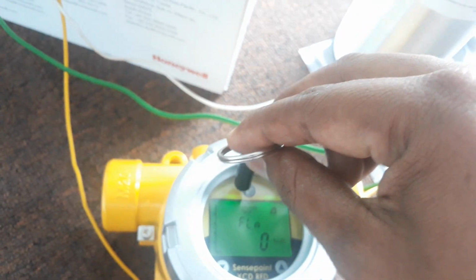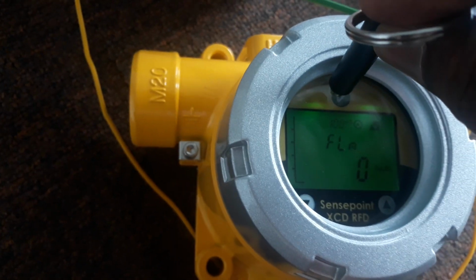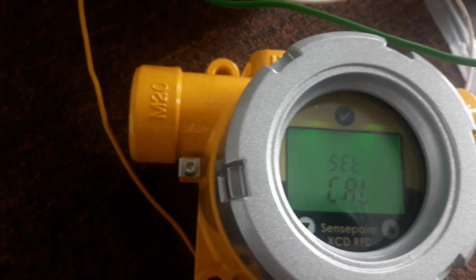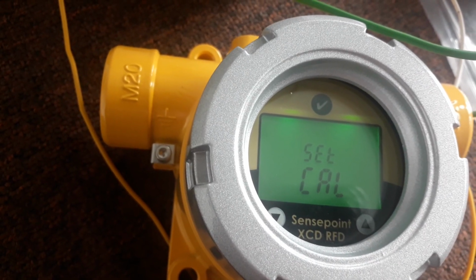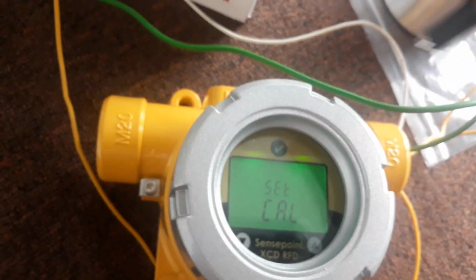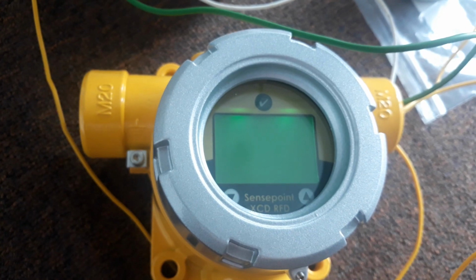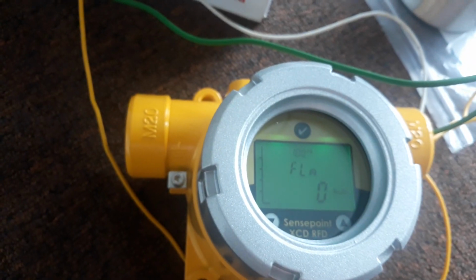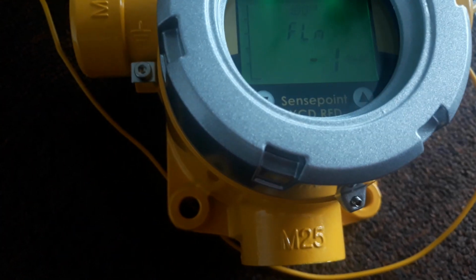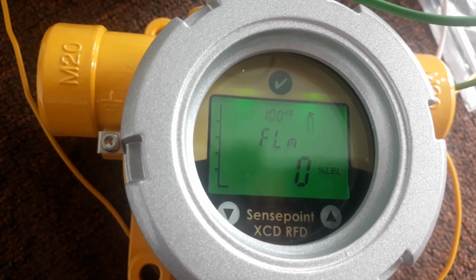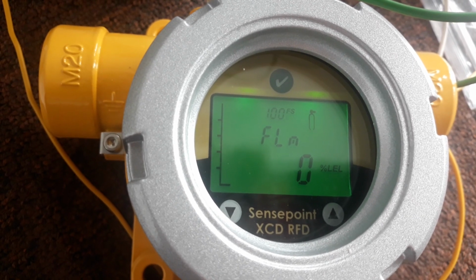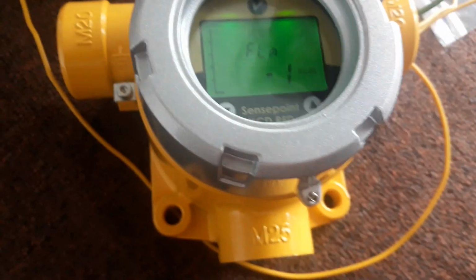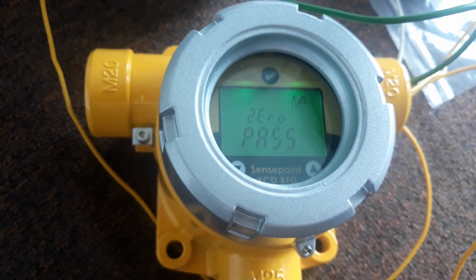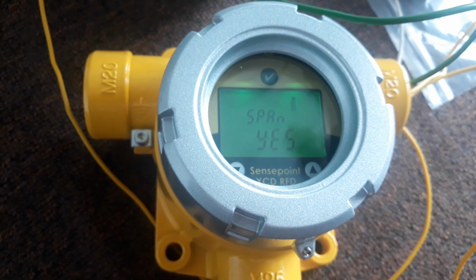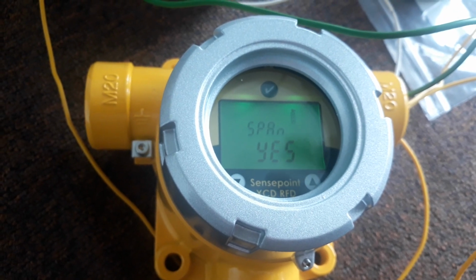So you push here until you see that button. The first page is set calibration. If you want to do the zero calibration, you touch here. And then the sensor starts doing the air zero. If the page looks something like this, you are nearly done. Okay, when the zero is stable, you touch the right button, zero pass. If it shows zero fail, it means you must repeat until you get a pass result.